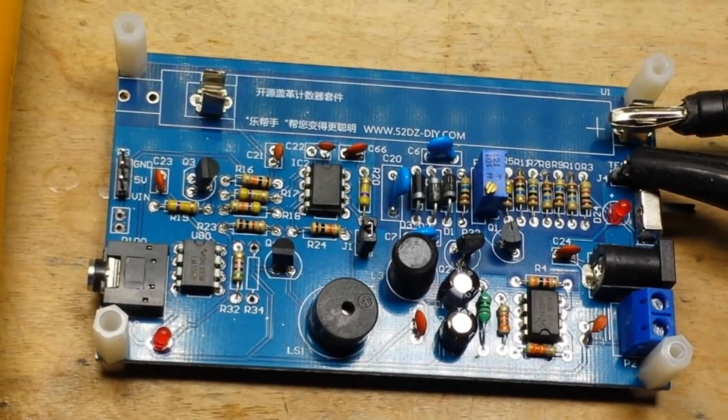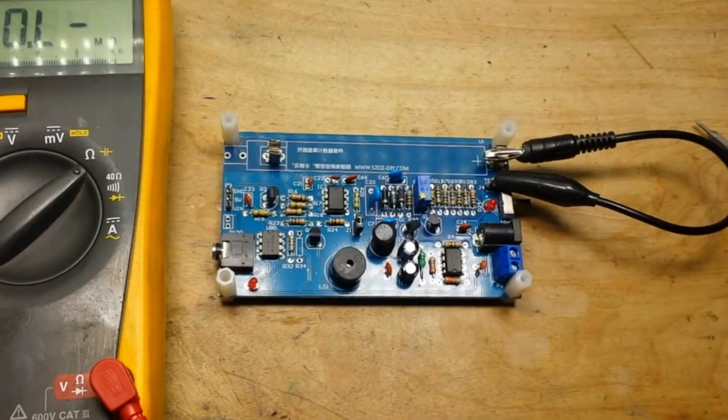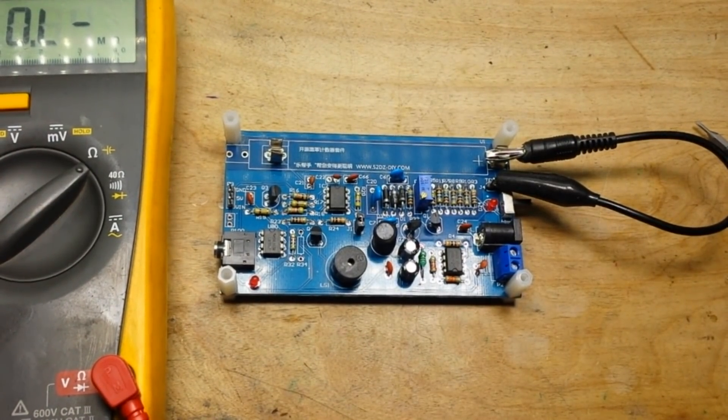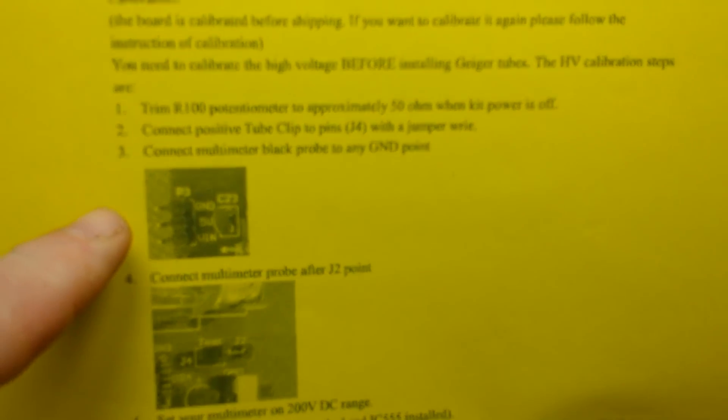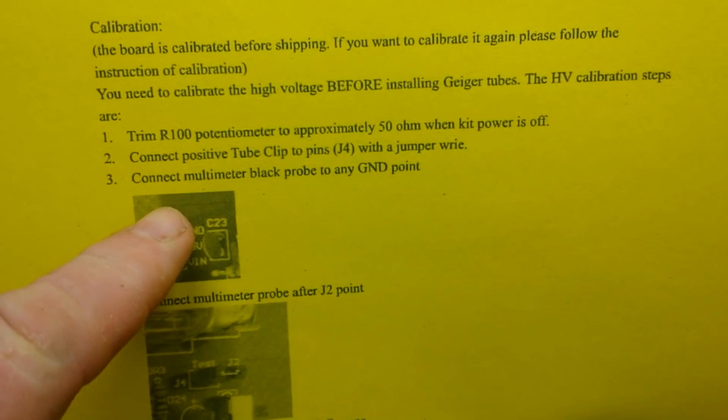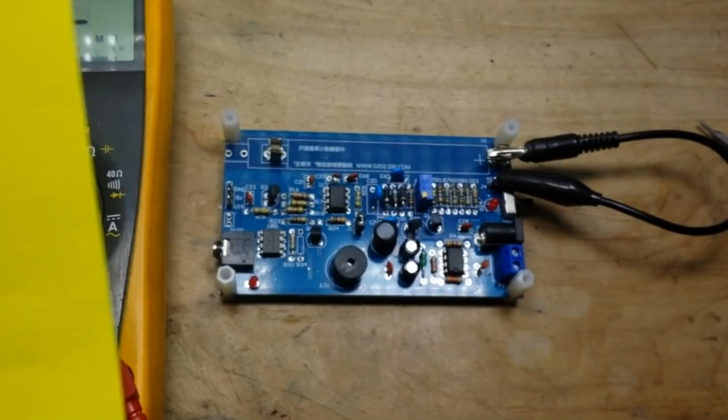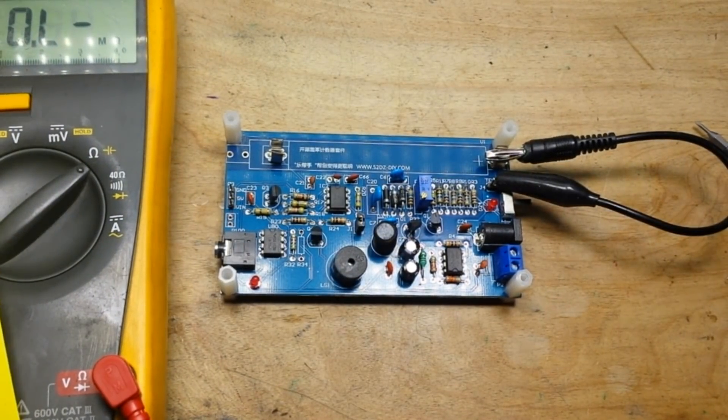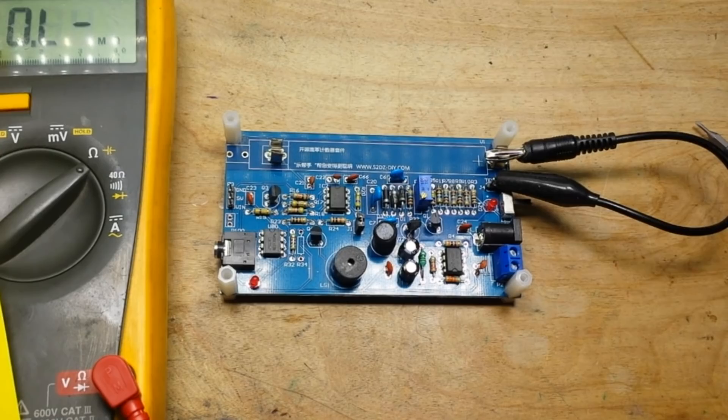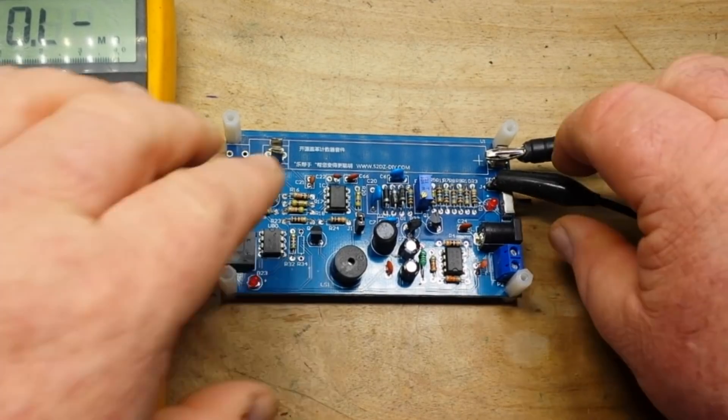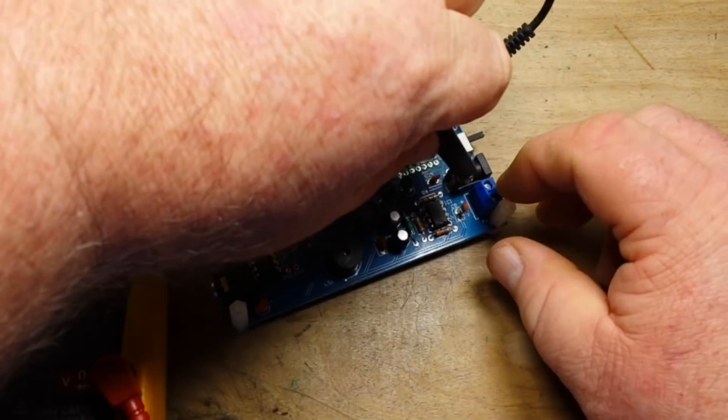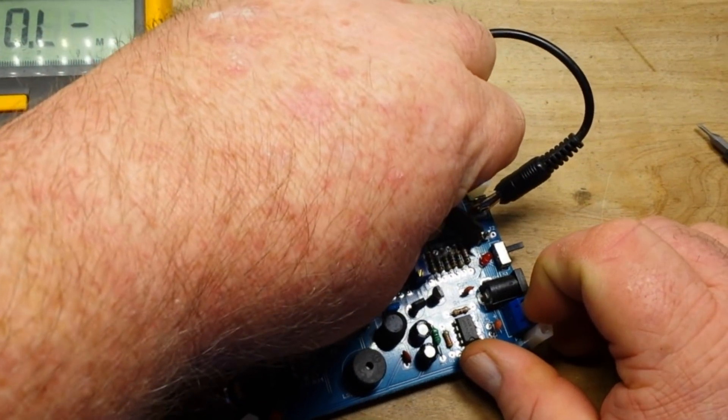Zoom out here a little bit. So our next step is connect multimeter black probe to any ground point. That's easy enough. Connect multimeter probe after J2. J2's down in there, so let's move this around.